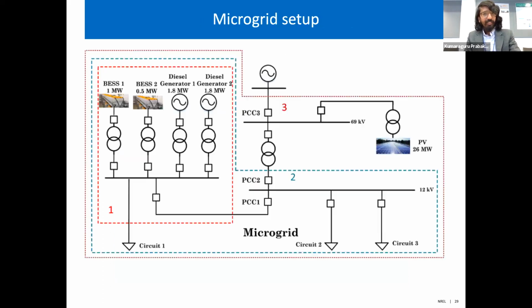This is the model we used for evaluating the microgrid controller. The main loads are supplied by a 69 kV substation, and there's a large PV plant at the 69 kV bus of almost 26 megawatts. The peak load for this microgrid was anywhere between 10 to 20 megawatts, so this has more than 100% renewable energy penetration. The microgrid also has a couple of diesel generators acting as voltage and frequency master, and a couple of battery energy storage systems. This feeds the microgrid circuit, which has multiple points of common coupling that can island the microgrid from the main grid if there's an issue on the grid side, and resync back once the grid comes back.